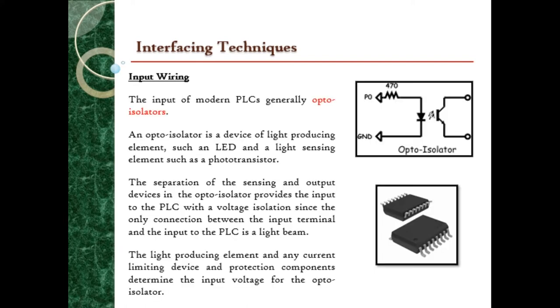Next, we are going to look into the input wiring that is normally used by the PLC. For a modern PLC, usually they use opto-isolators. So what is an opto-isolator? An opto-isolator is also called an optocoupler, photocoupler or optical isolator. It is an electronic component that transfers electrical signals between two isolated circuits.